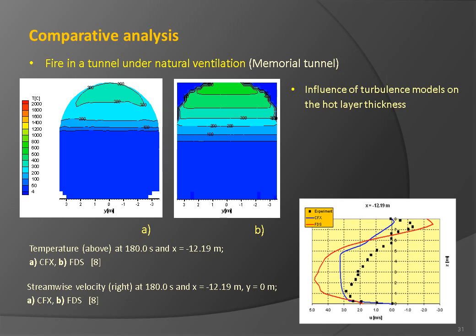In the figure below, flow velocities are compared for one of the locations, 12.19 meters south of the fire. In both cases, CFD results do overpredict the flow velocity induced by the fire.